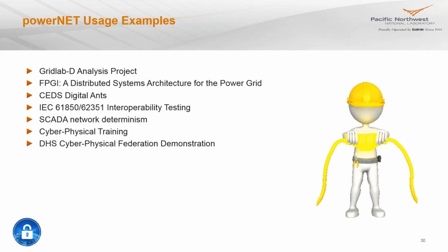I think there is an assumption in the field that many of us all share that SCADA networks are far more deterministic than IT networks. And I still believe that to be true, but that was a widely held assumption that had very little testing to back it up. So we actually did a rigorous, precise experiment under controlled conditions to see truly how deterministic SCADA traffic is. And the answer is, of course, it depends. But they were counterintuitive results.